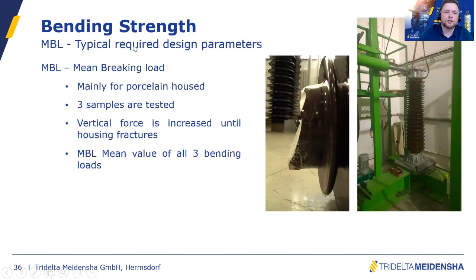For porcelain housed surge arrestors, typically the value MBL plays a role, mean breaking load. So normally 3 samples are tested, and you apply a force vertically. On the picture here on the right side, you can see this cylinder, this hydraulic actuator pushing the surge arrestor on the top. And at a certain point, the porcelain will break, and you record the force or the moment which is created on the bottom terminal. And the mean value of those 3 breaking loads is the MBL value. So MBL value means the mean value of all 3 breaking loads.